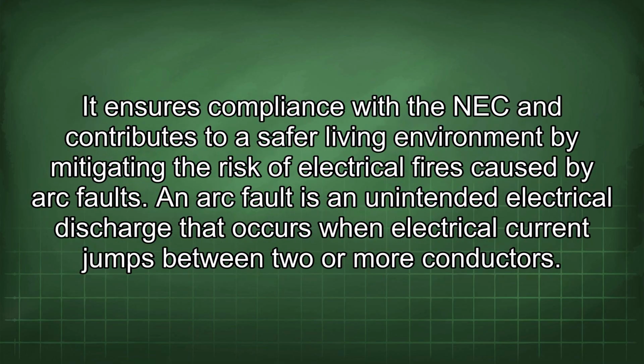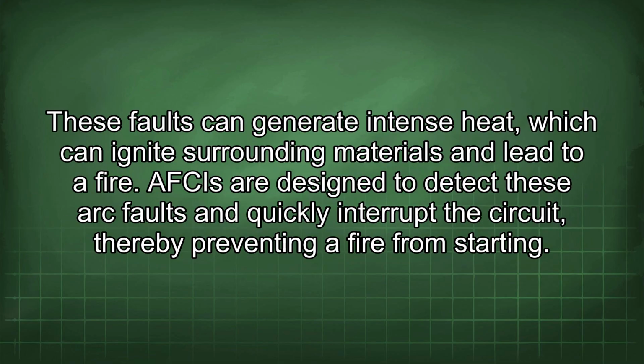It ensures compliance with the NEC and contributes to a safer living environment by mitigating the risk of electrical fires caused by arc faults. An arc fault is an unintended electrical discharge that occurs when electrical current jumps between two or more conductors. These faults can generate intense heat, which can ignite surrounding materials and lead to a fire. AFCIs are designed to detect these arc faults and quickly interrupt the circuit, thereby preventing a fire from starting.